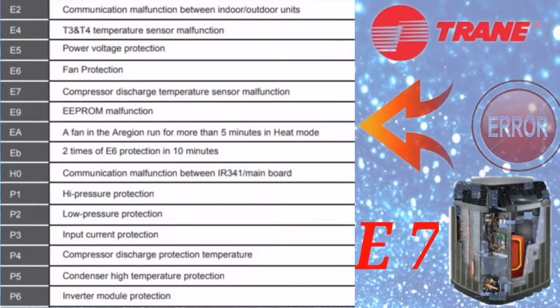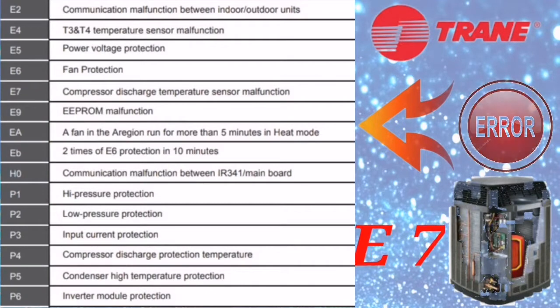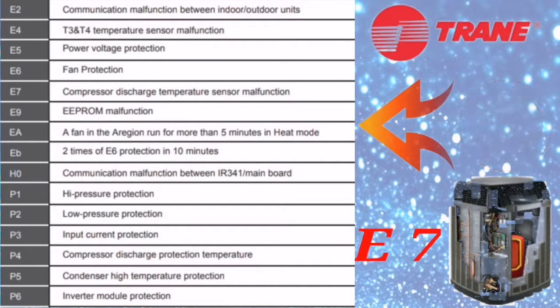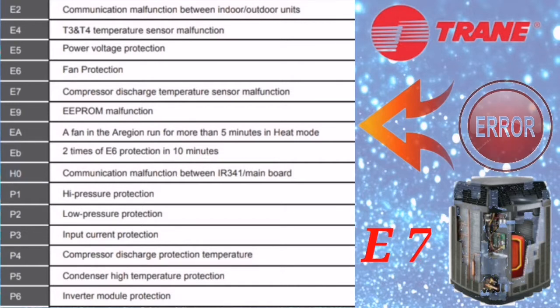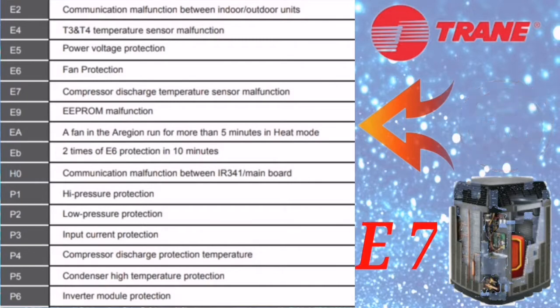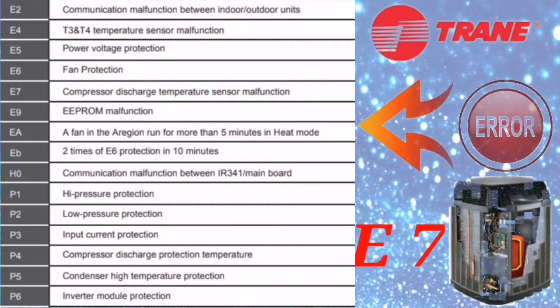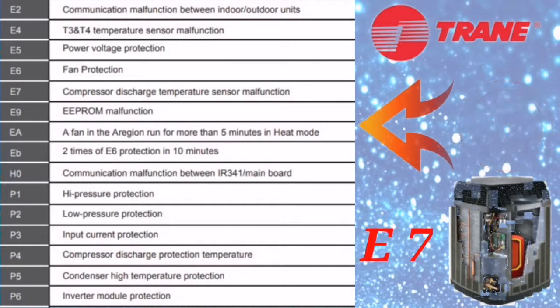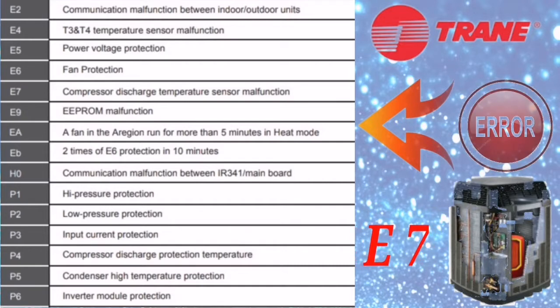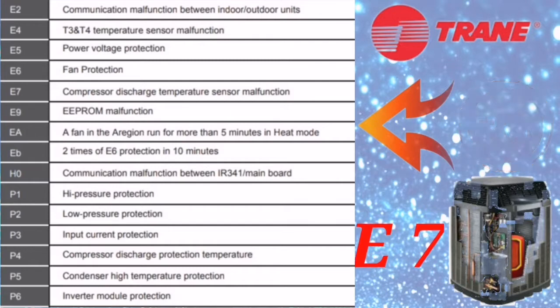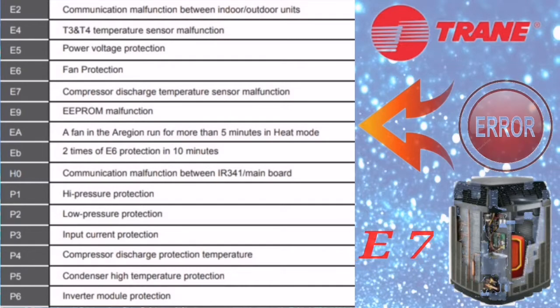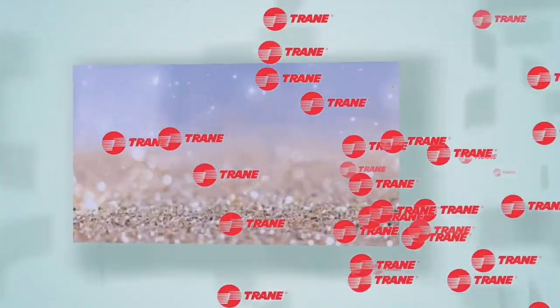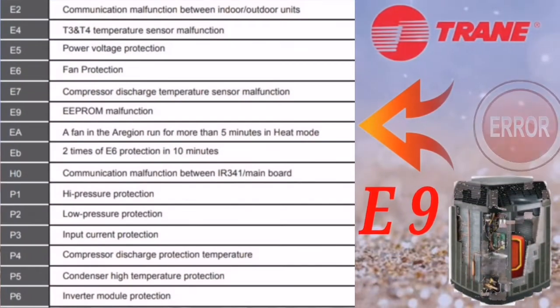The next error code is E7, which means compressor discharge temperature sensor malfunctioning. For this error, check only the sensor components. First, check the resistance of the sensor, then check the placement and the cable coming from the outdoor PCB to the sensor for any cuts or damage. Then check if the outdoor PCB is giving proper supply to the sensor — if not, the outdoor PCB needs to be changed.